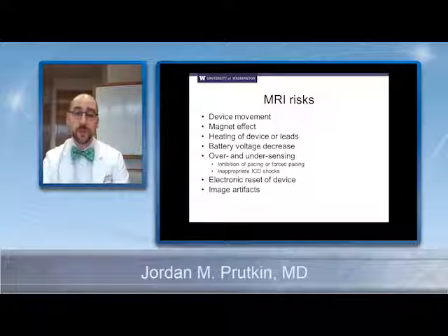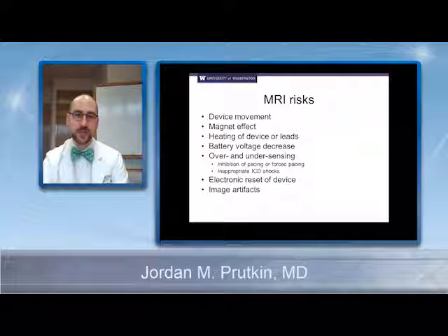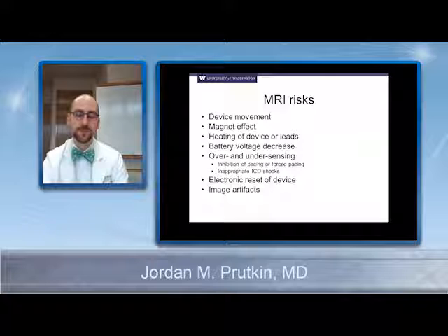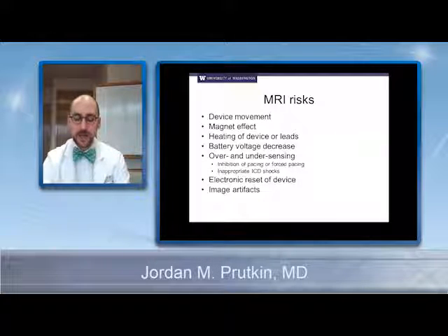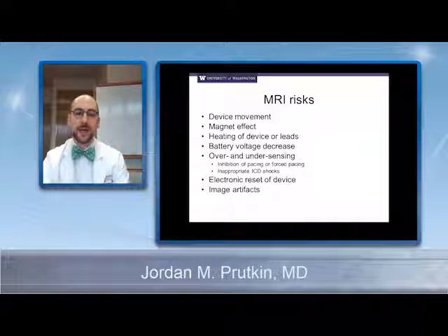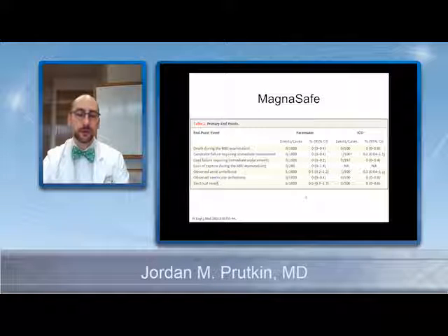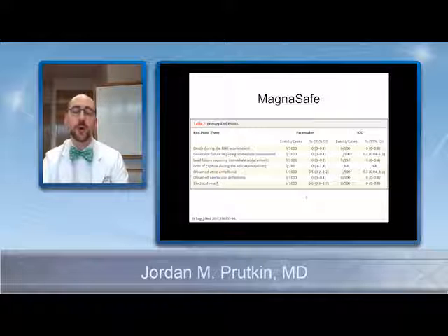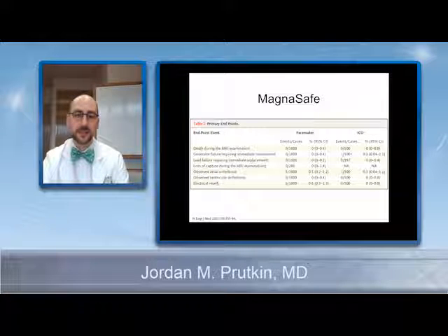Another concern would be oversensing with defibrillators, and if you don't make the appropriate settings adjustments, someone could get shocked by the defibrillator because the device thinks that someone is in ventricular fibrillation. One of the other concerns would be electronic reset of the device. So I think of it as a software reboot back to factory settings. And if you have a reset of a device, it can be quite a big deal. And then artifacts. This is another issue, imaging artifacts, that the quality of the picture may not be at the level we'd like it to be.